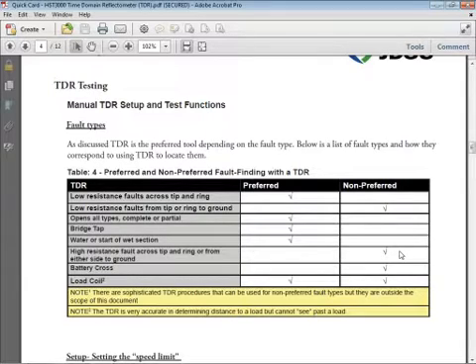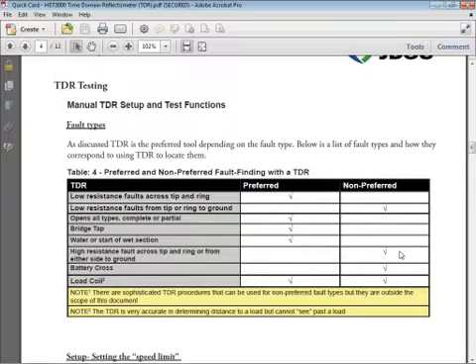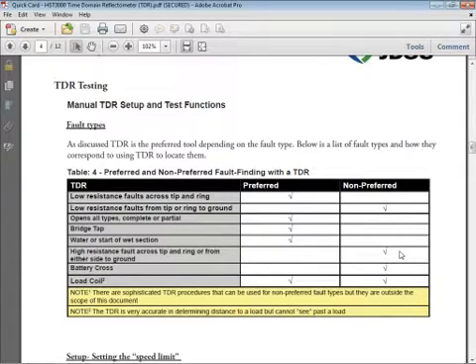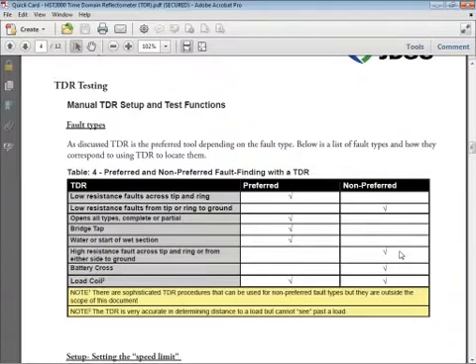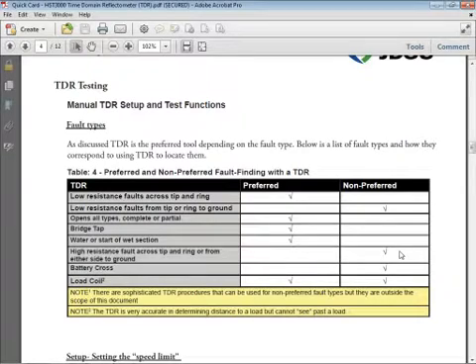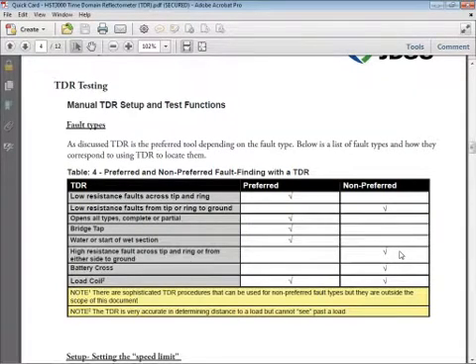Low resistance faults from tip or ring to ground — TDRs are not all that good at doing stuff to ground. When you think about it, they work across tip and ring. You hook a TDR up across tip and ring. There are some sophisticated techniques you can employ to look for a ground, but they're beyond what we're going to talk about in today's introductory session. Opens of all types — this is where the TDR really shines. It's the heavyweight champion of the world for opens: double-sided opens, single-sided opens, high resistance opens, or series faults. TDR is very good at all of those.